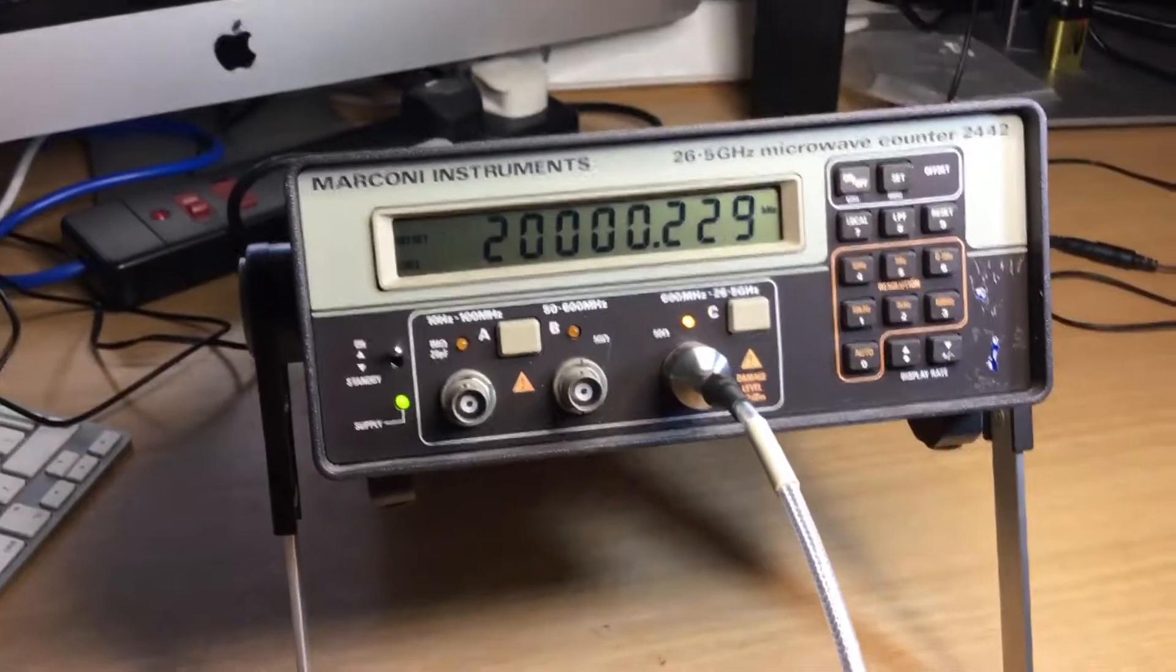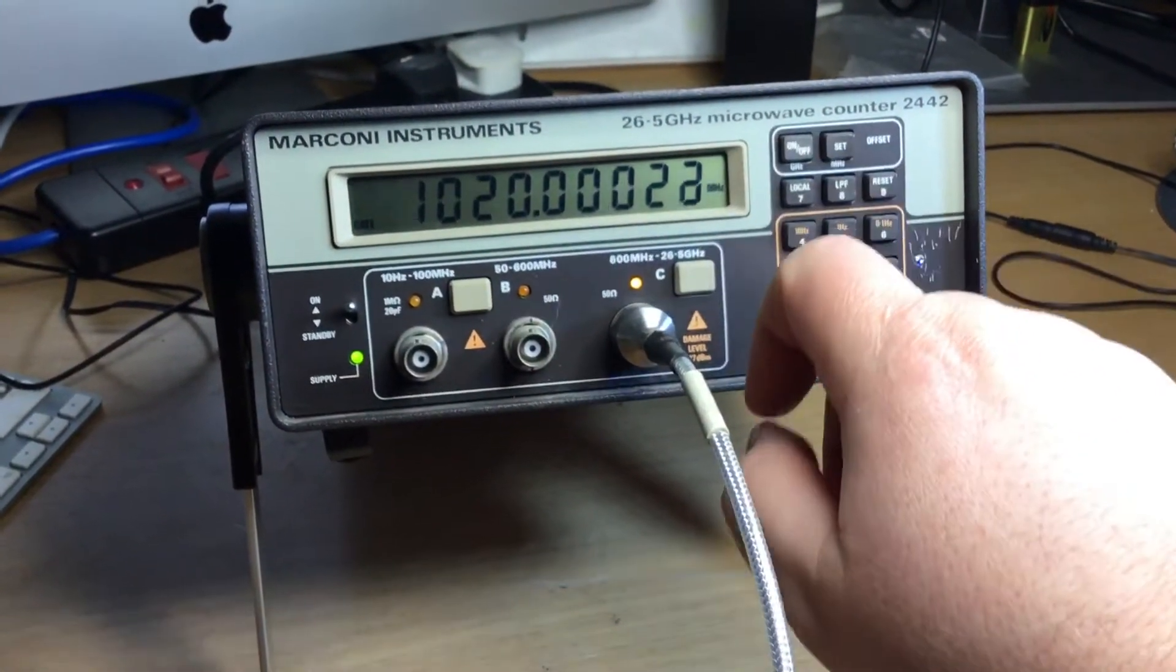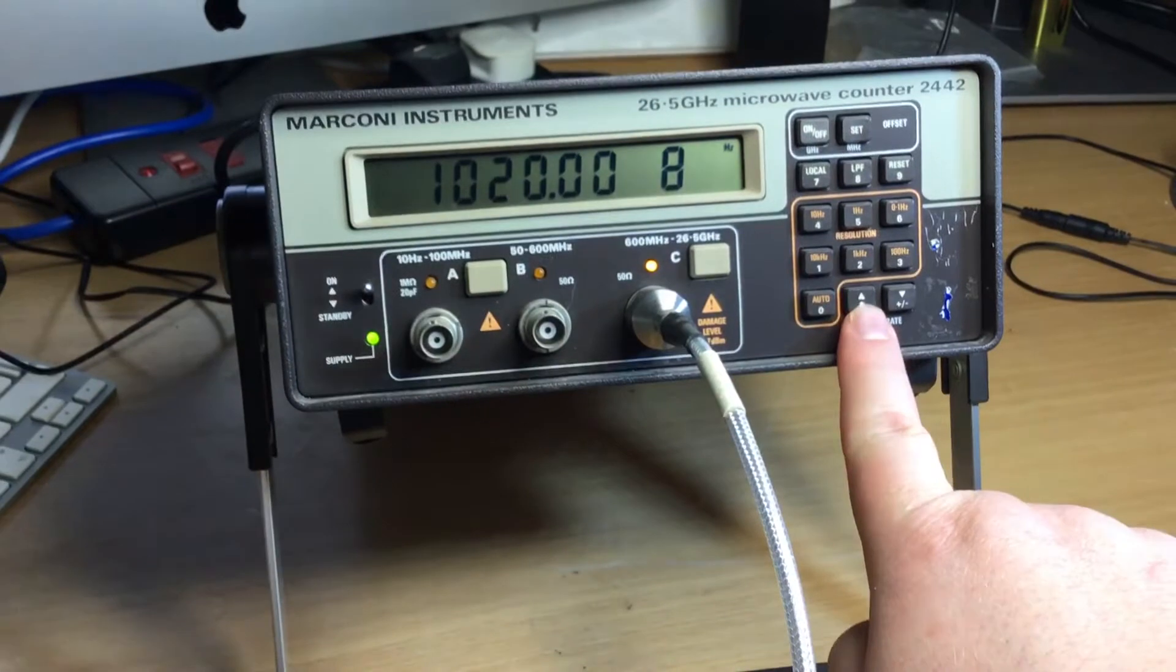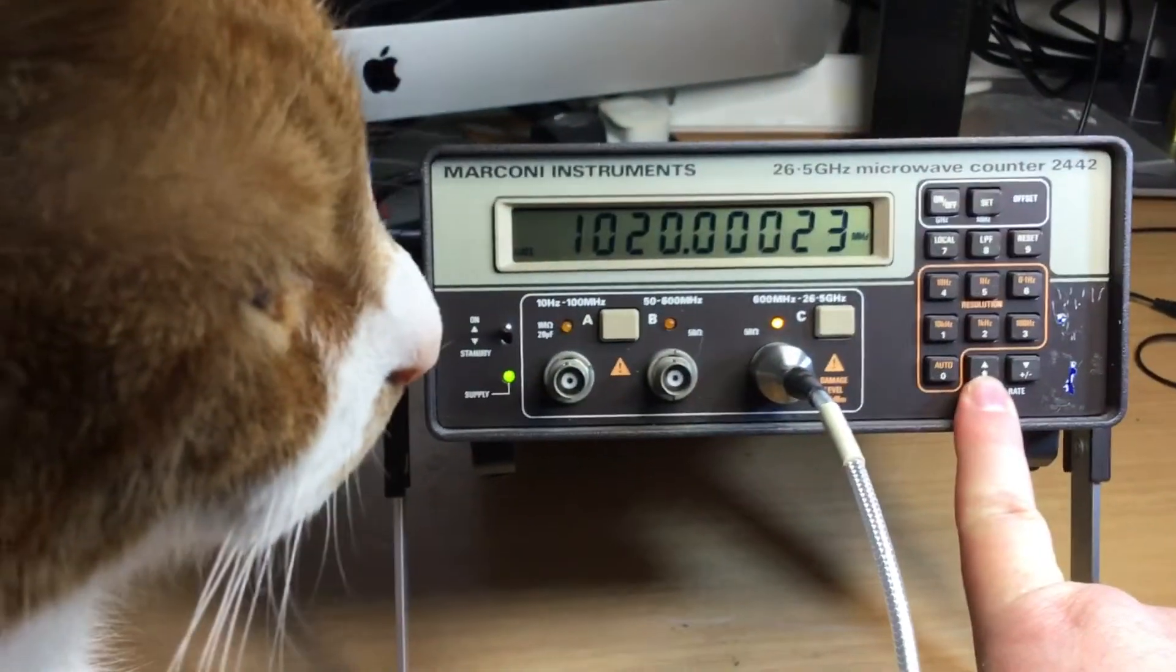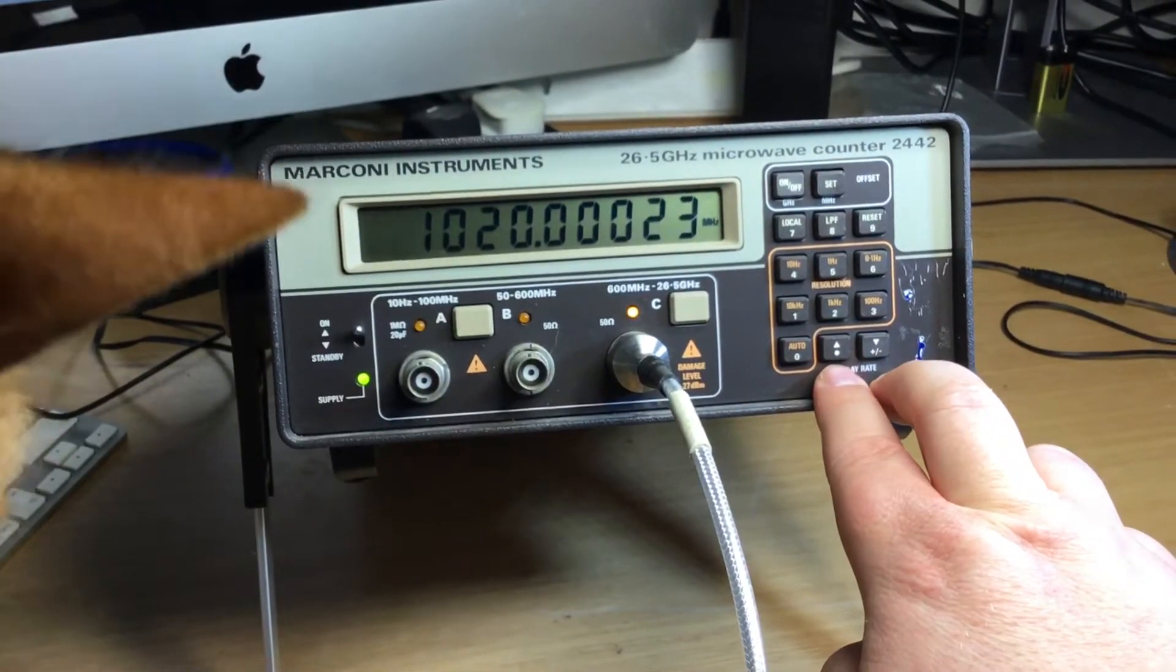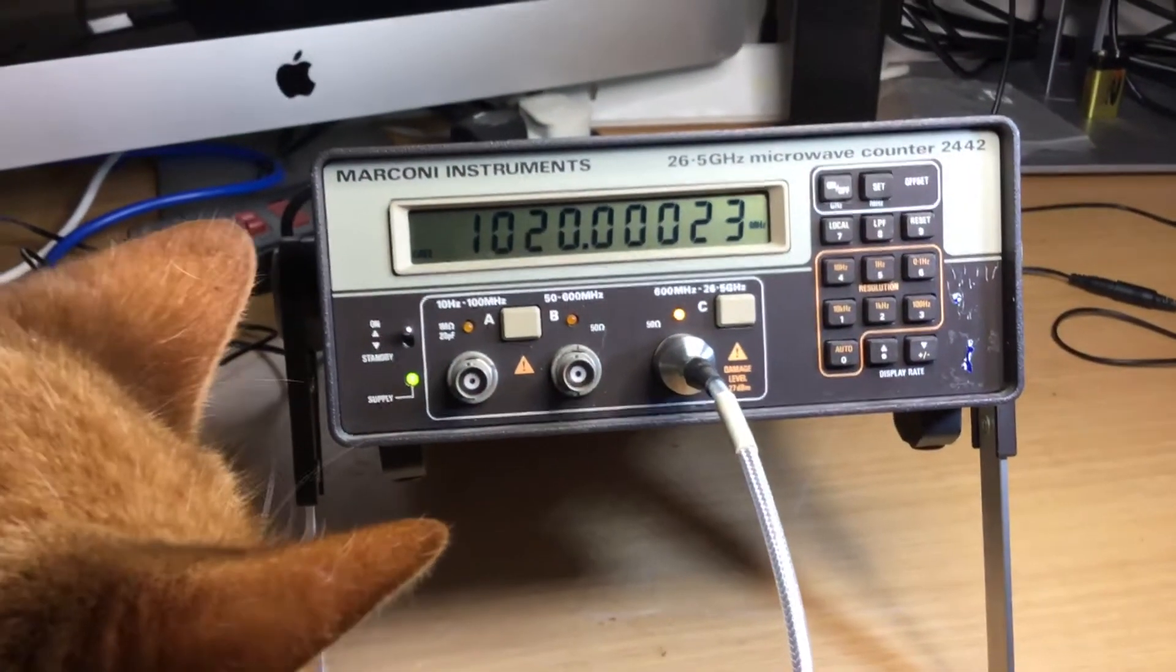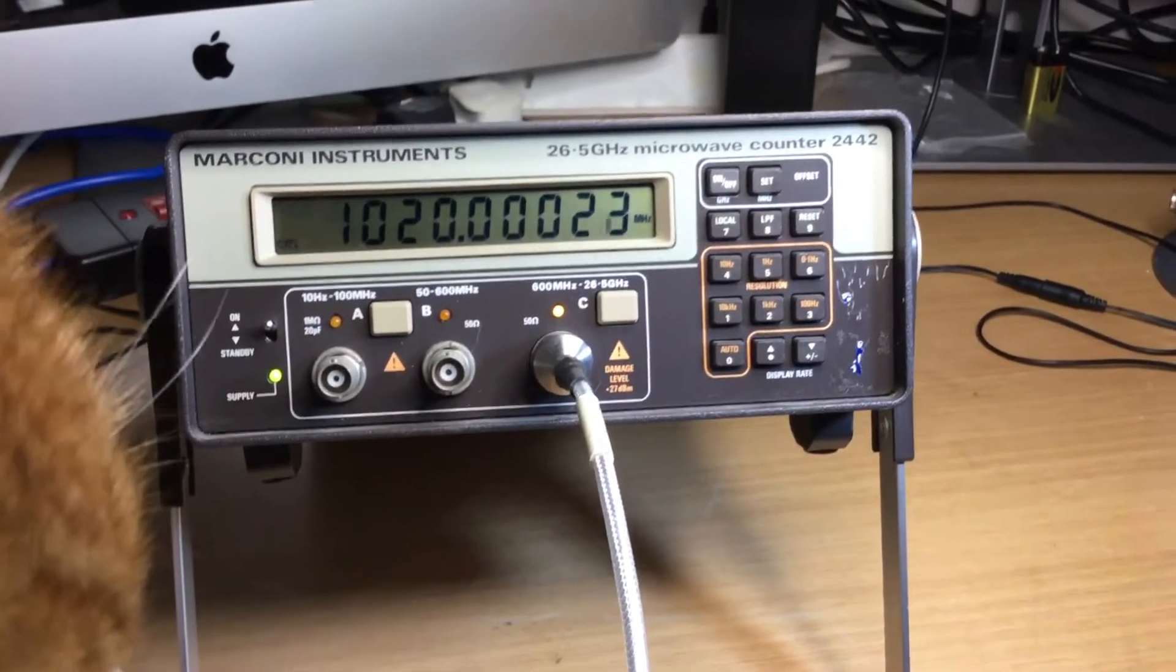There's a number of measurements that you can perform here, or you can just go back to standard frequency readout, which is what we're doing there. We're reading a thousand and twenty megahertz. You can select the resolution. F is fastest frequency measurement. And then we're down to a slower resolution and then back up to the fastest resolution. That's the fastest that the instrument will do.